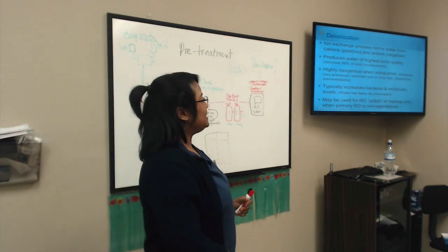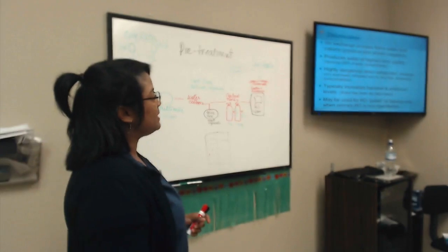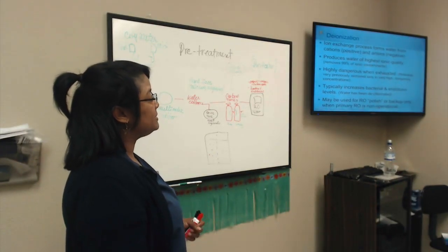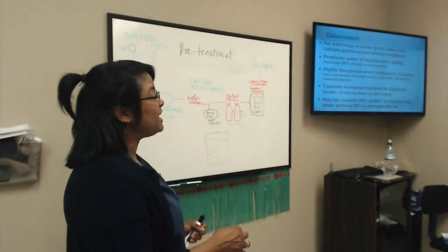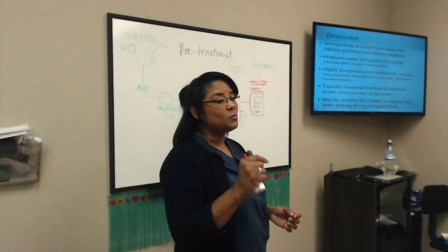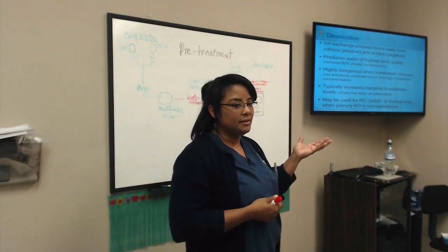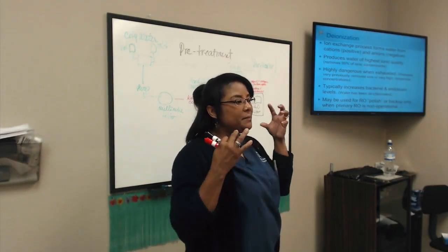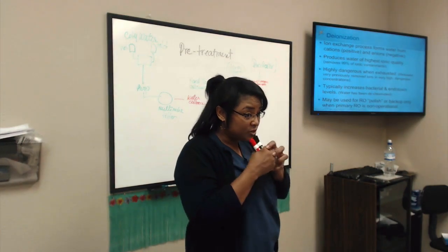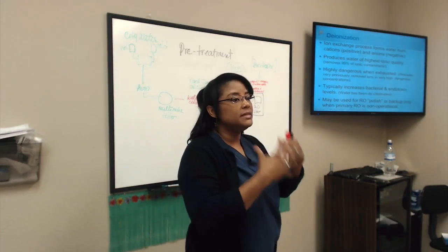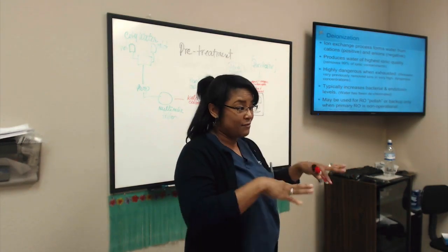Okay? In this case, it produces water of the highest ionic quality. It removes 99% of the ionic contaminants. It's highly dangerous when exhausted. That's why we don't normally use it all the time, okay? Because of its capacity, once it is exhausted, it starts releasing everything that it had filtered.